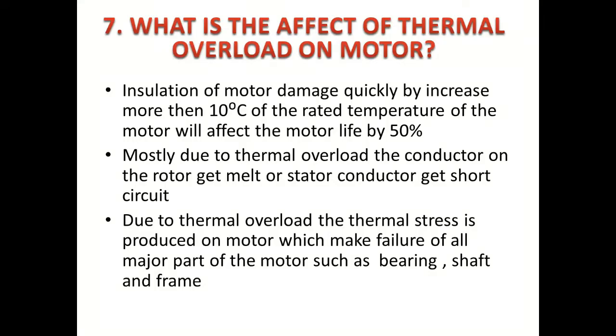Next, we are going to see the effects of thermal overload on a motor. The main and major effect is insulation damage, which leads to short circuit. If the temperature increases more than the rated value, by every 10 degrees Celsius of temperature increase, the motor lifetime will decrease by 50%. For example, if the motor is rated to run for 1000 hours, and you exceed the ambient temperature by 10 degrees, your 1000 hours will reduce to 500 hours. You can have various insulation classes — A, B, F, H — from 105 degrees Celsius to 180 degrees Celsius ambient temperature; choose according to your working area.